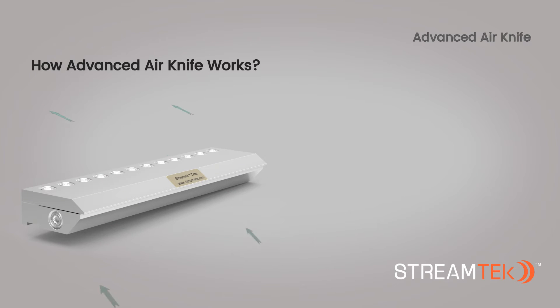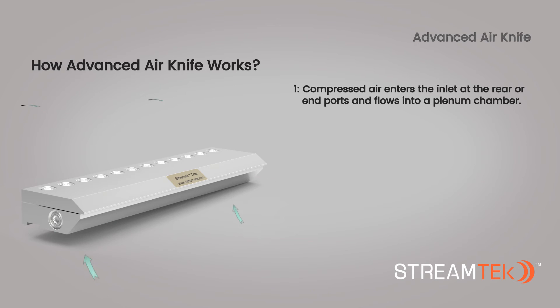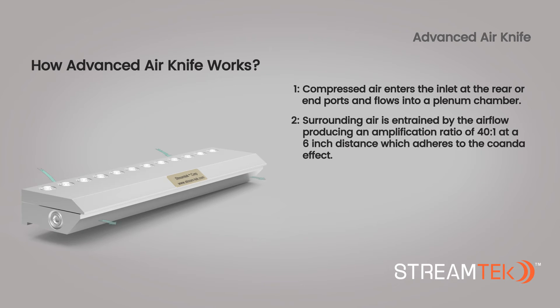How does a Streamtek Air Knife work? Compressed air enters the inlet at the rear or end ports and flows into the plenum chamber. Surrounding air is entrained by the airflow, producing an amplification ratio of 40 to 1 at 6-inch distance, which adheres to the Coanda effect.